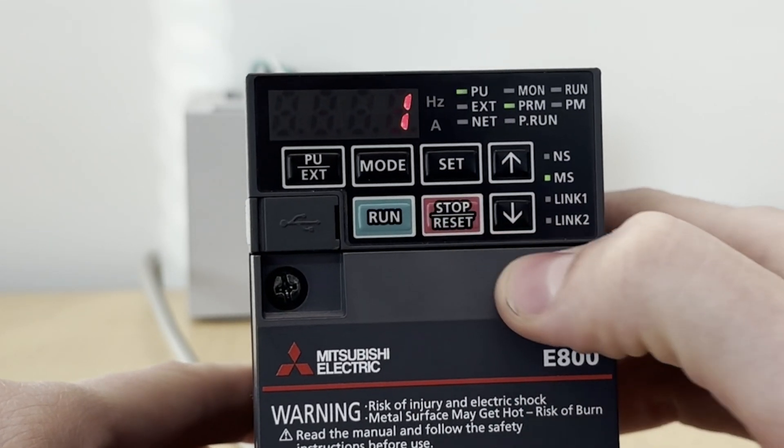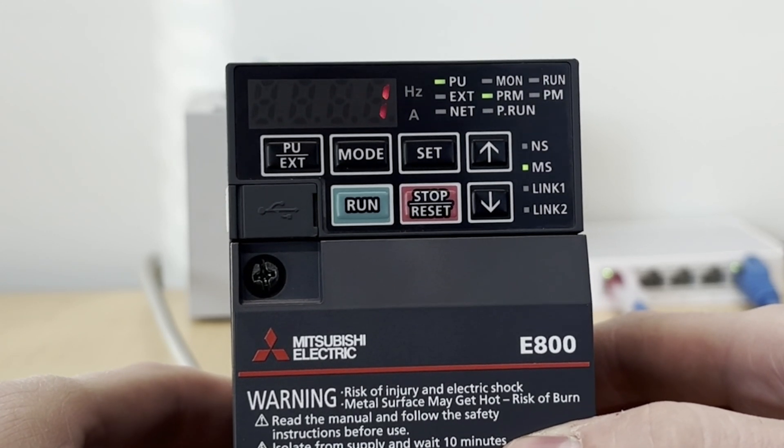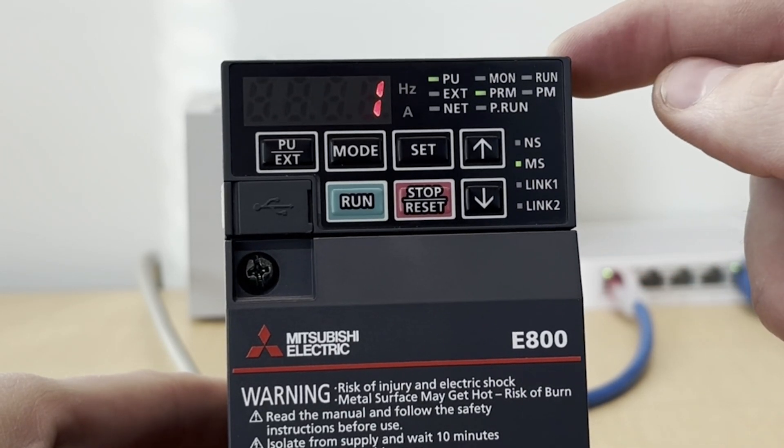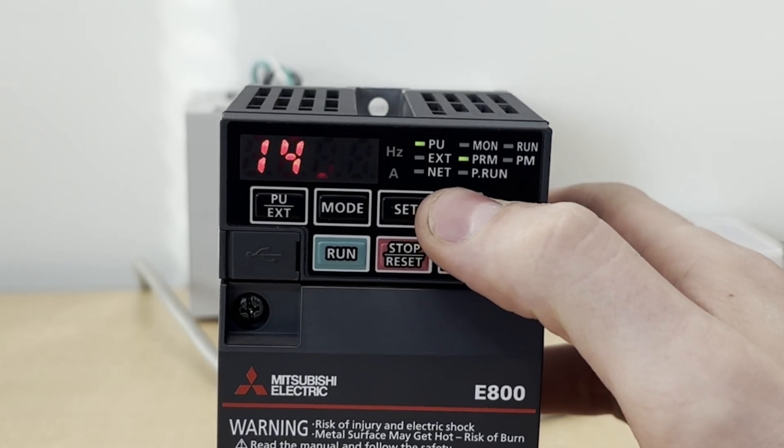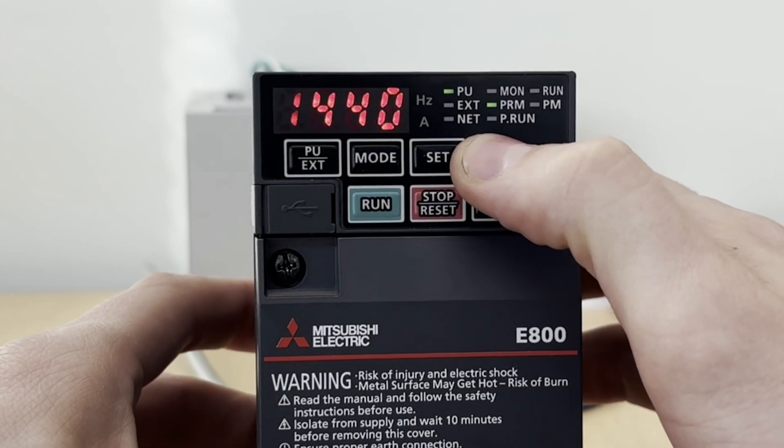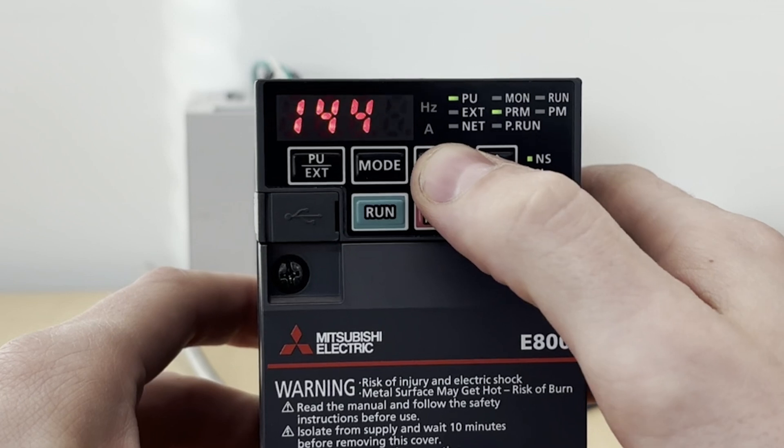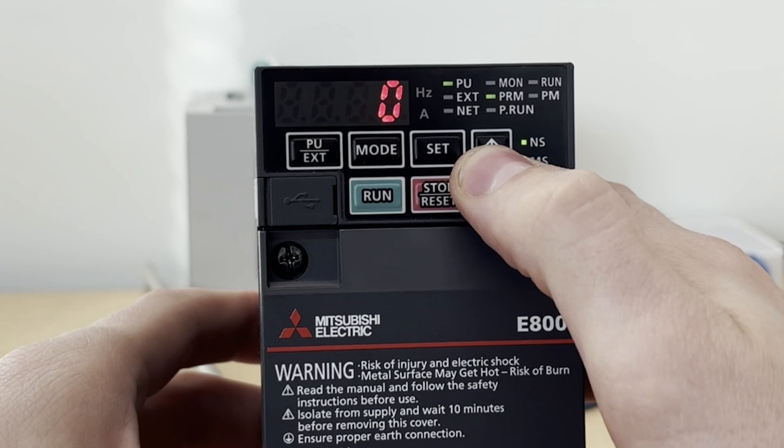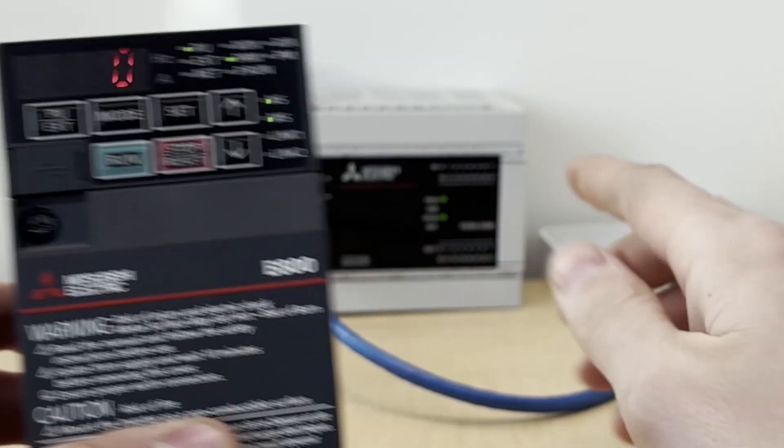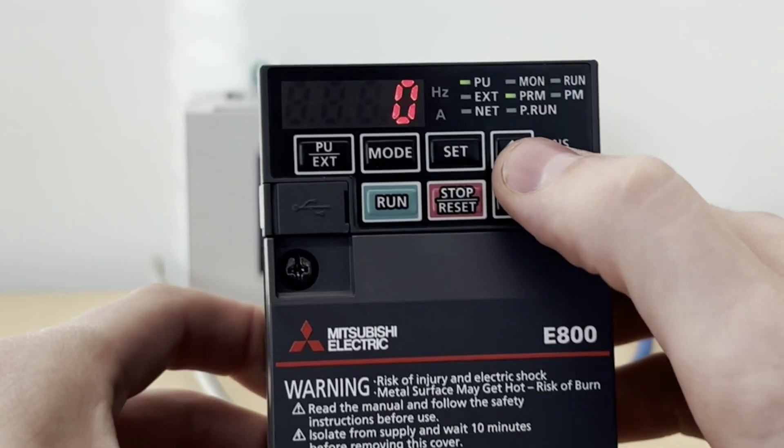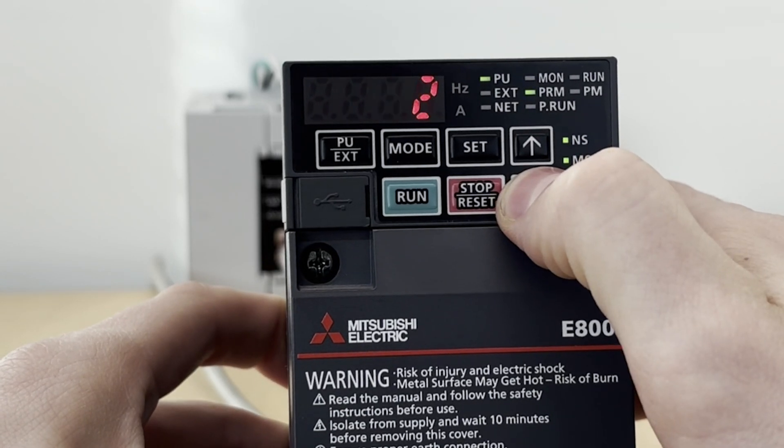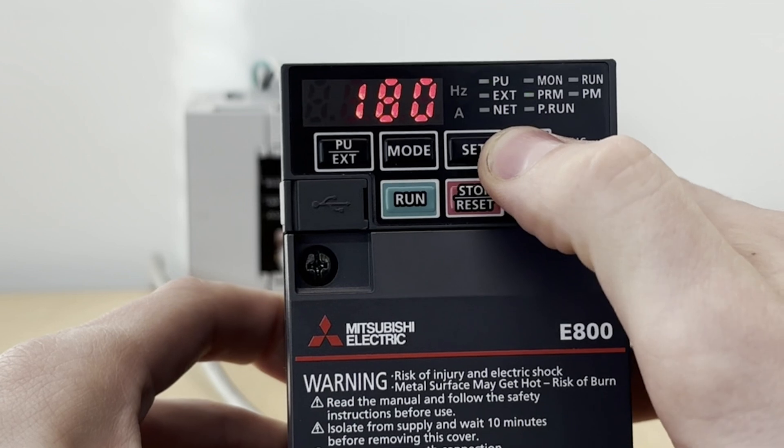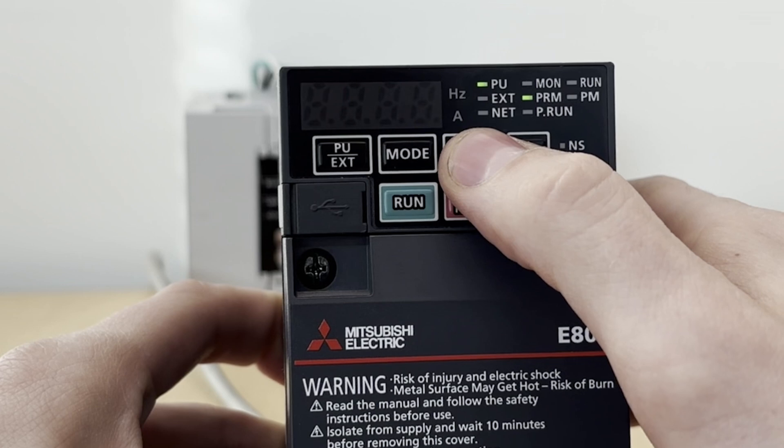Finally we need to set up the IP address of the device that's going to be controlling or sending Ethernet commands to this inverter. That is going to be parameter 1449 through 1452. 1449 is set at zero. By default these will all be zeros, meaning it will not accept Ethernet commands from any source. We want it to be set to the IP address of the CPU module, which is going to be 192.168.3.250.